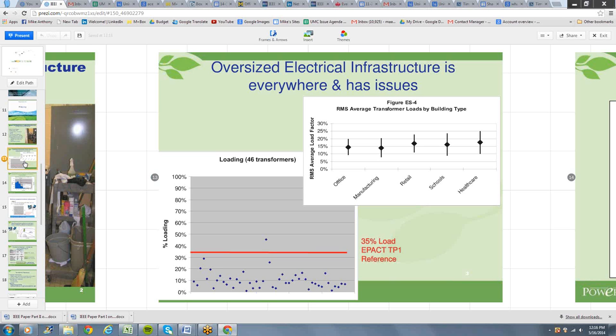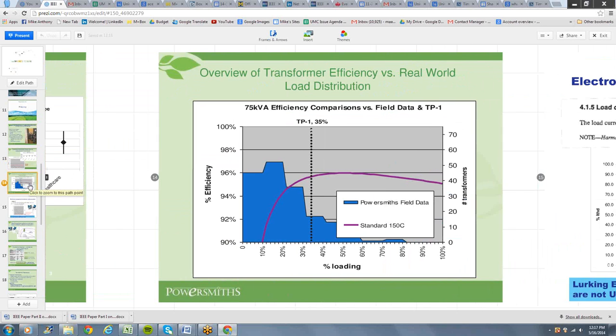So that's one takeaway. The second takeaway is that, whoa, we're talking about 15, 20% loading. So we're talking about an electrical infrastructure that is as much as 5 times oversized. We're seeing the same. We're out in the field replacing transformers all the time. Bottom left, you can see the scatter plot of loading of transformers. You can see we're down in that same kind of load range. And particularly, what I've done is overlay the 35% loading level, because dry type transformers are regulated, so there's a minimum legal efficiency, and that is referenced at 35% loading, which, as you can see, is not exactly relevant to the population of transformers. And we'll see on the next slide why that's important.